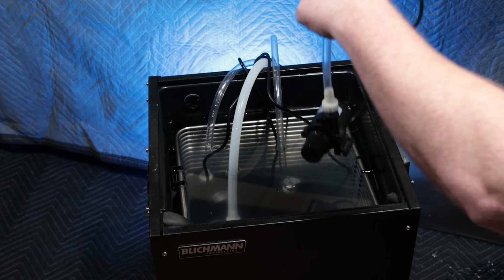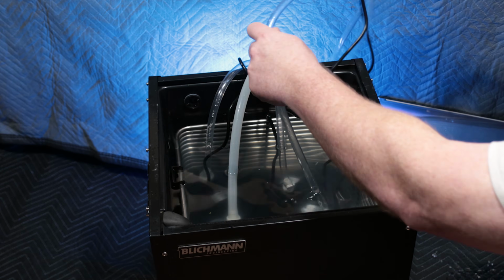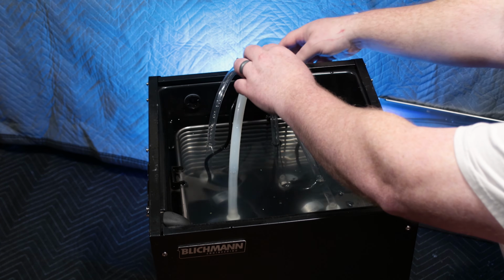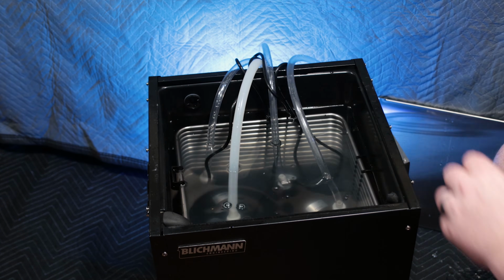So setting up the unit is pretty simple. All you need to do is just put all of your pumps with the hoses pre-attached to them, hang the wires over the back side. Once you've got all of your hoses in attached to the pumps, then you need to put all your return hoses in. And then once you have that done, you can go ahead and put the cover back on the front, which is the Glycol reservoir cover.